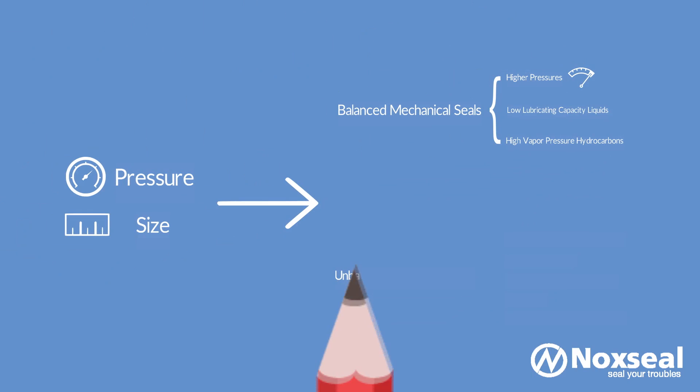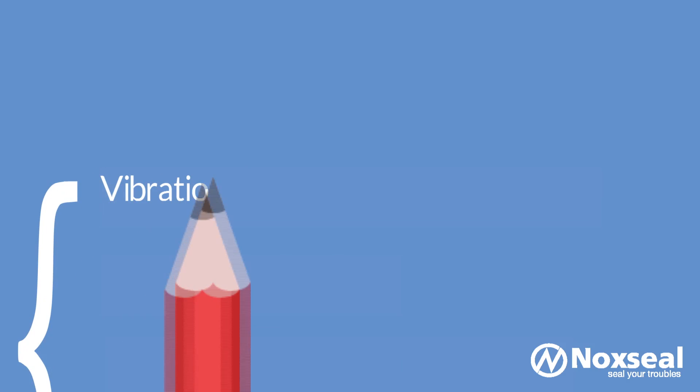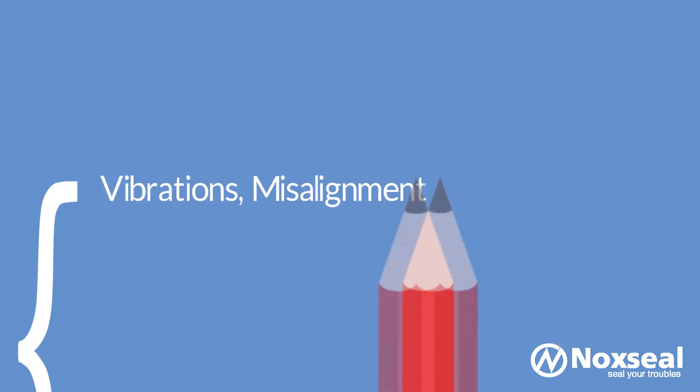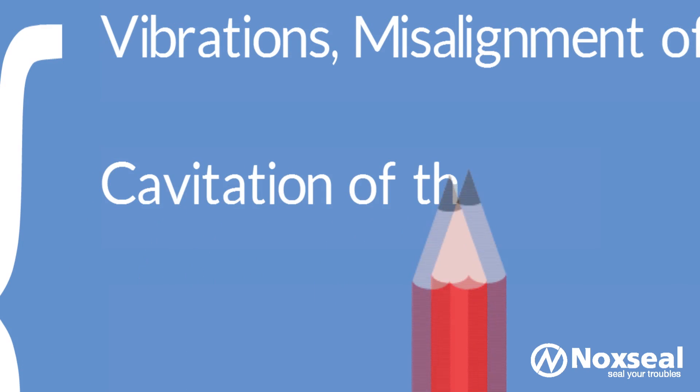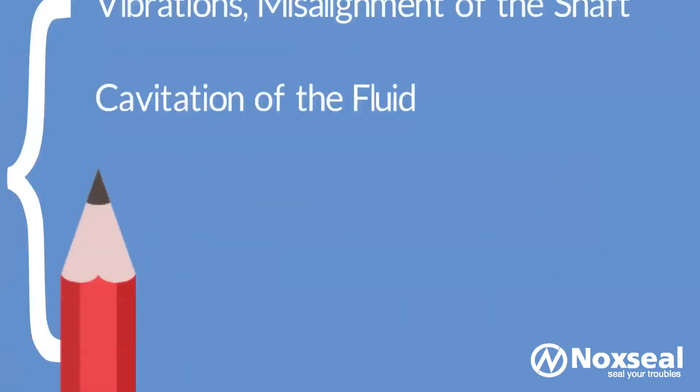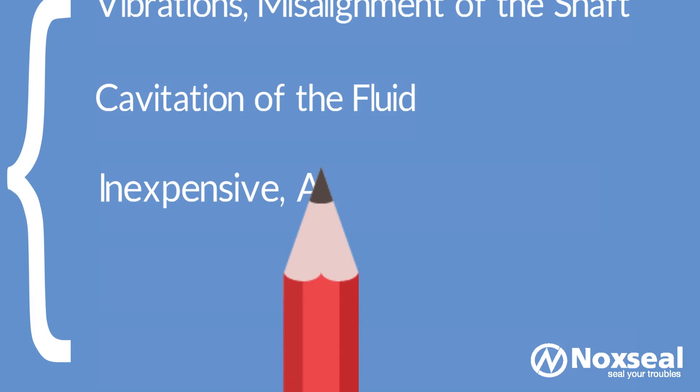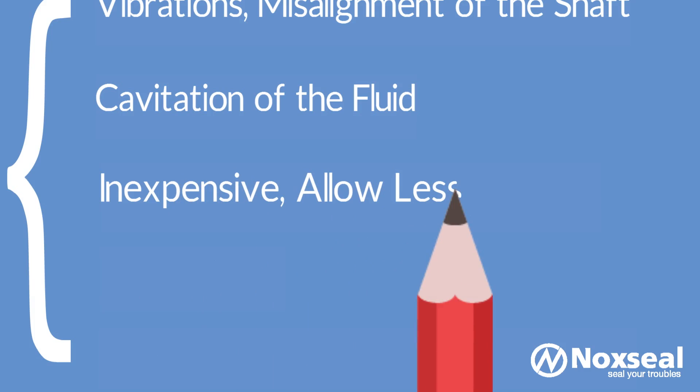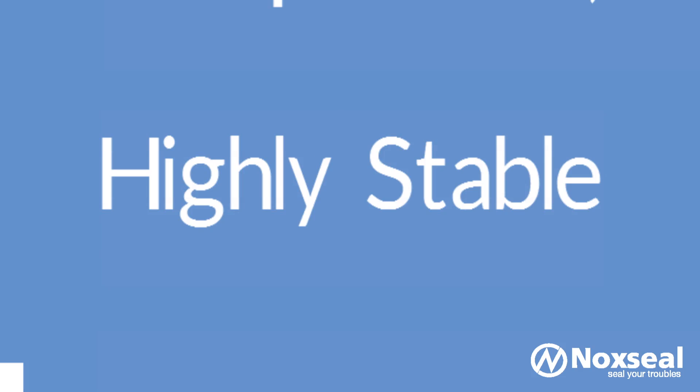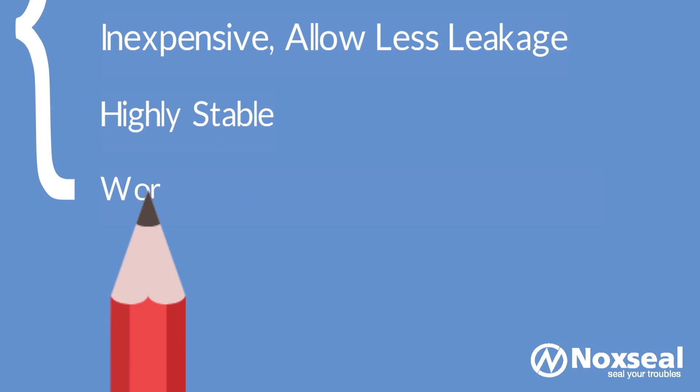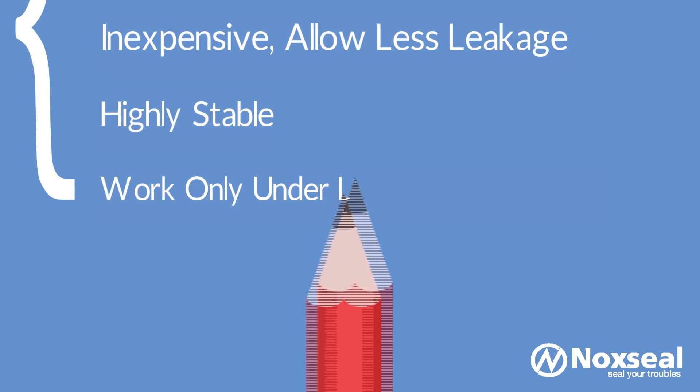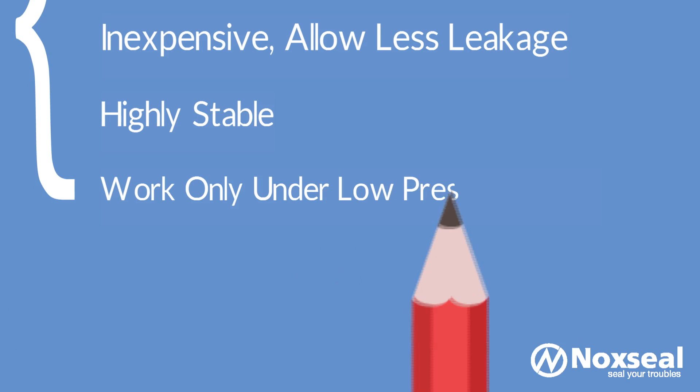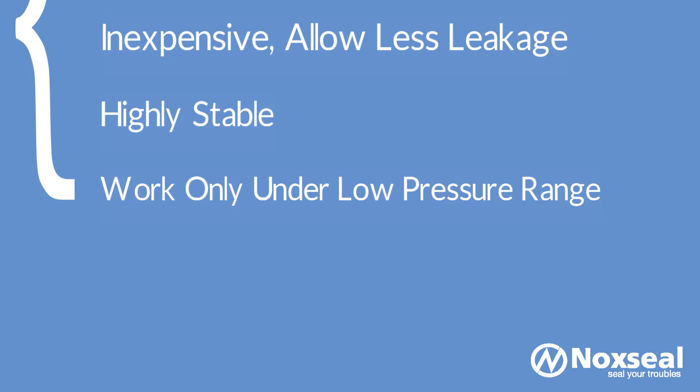Unbalanced mechanical seals are used under drastic conditions where there are vibrations, misalignment of the shaft, and cavitation of the fluid. Unbalanced mechanical seals are inexpensive, allow less leakage, and are highly stable. However, these seals work well only under low pressure range. If the liquid force exceeds certain limits, the lubricating film between the faces squeezes out and the seal fails.